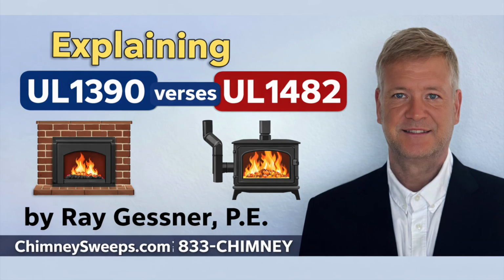If you try to slide a freestanding room heater tested to 1482 into a tight masonry fireplace without the proper 1390 testing, the inspector could fail it instantly. And if the inspector fails it, your homeowner's insurance carrier is going to invalidate your fire coverage. Insurance companies underwrite the risk of your home based entirely on the assumption that you are strictly adhering to these recognized safety standards. So don't guess. Ask your retailer. Ask your inspector.